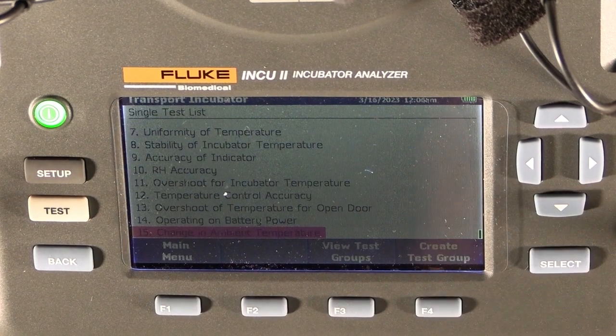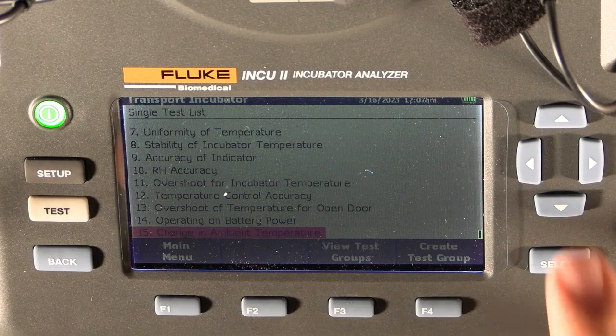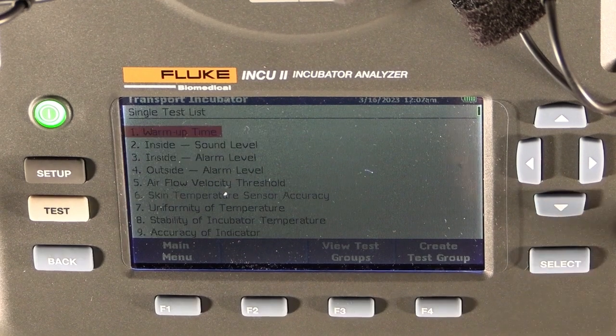And then lastly, we do an ambient temperature change. What we do is the same as we did for the stability test of the incubator. We now take it into a room with a 21 to 25 degrees Celsius ambient temperature and redo that temperature stability test to see whether the machine performs in the same manner in a lower temperature area. Remember that a transport incubator will go into a hospital, outside the hospital, into an ambulance. So we have to make sure that it will operate accurately in all those conditions.